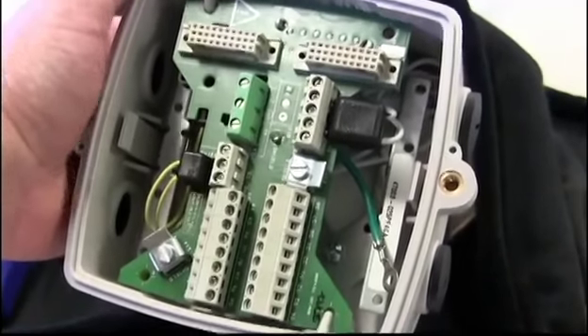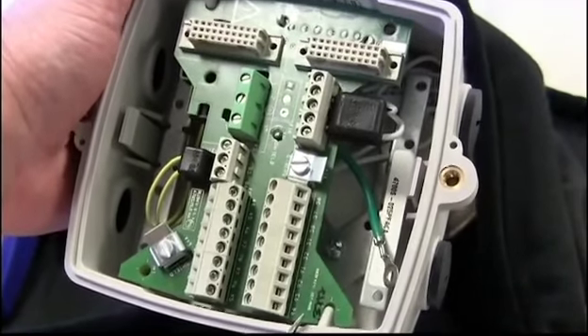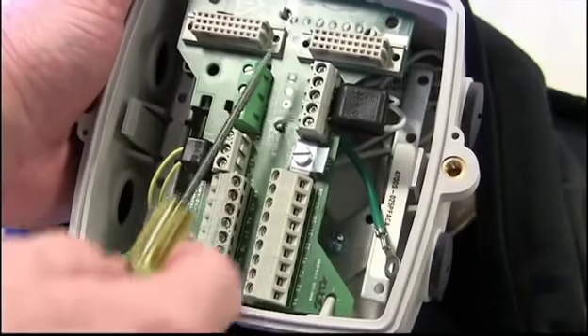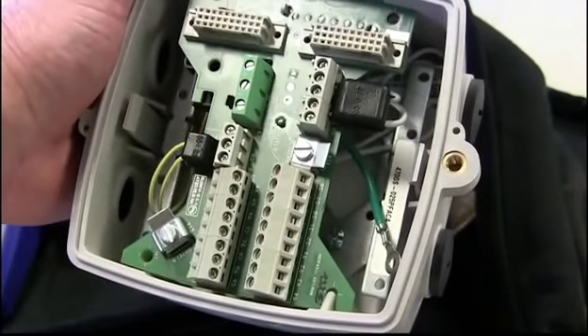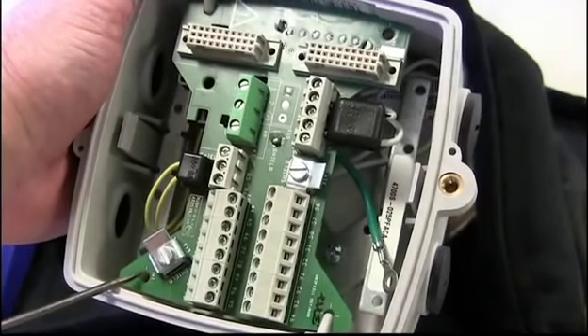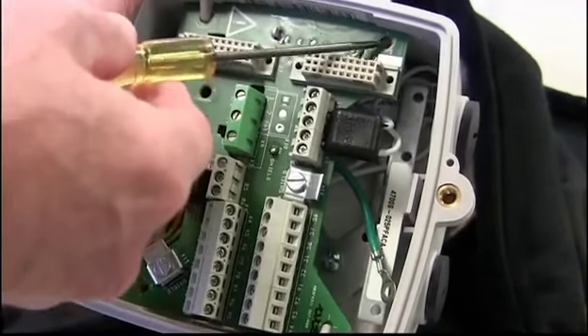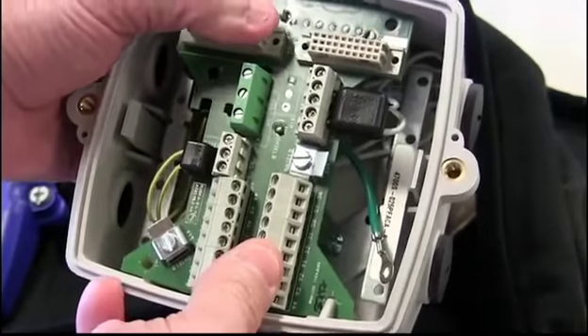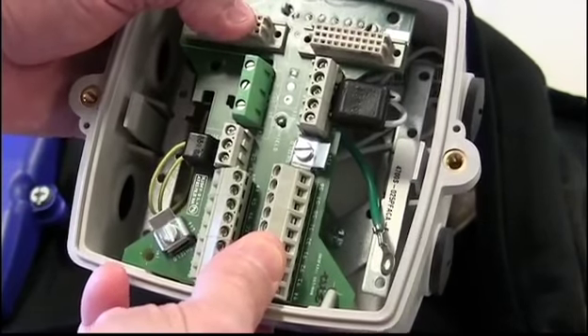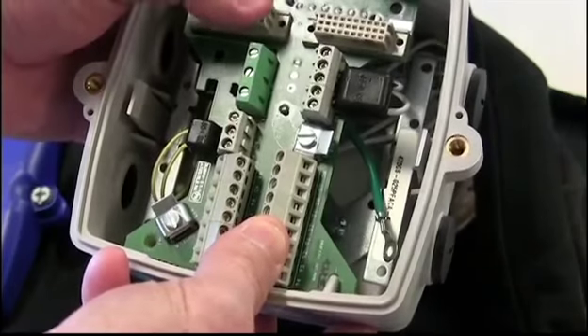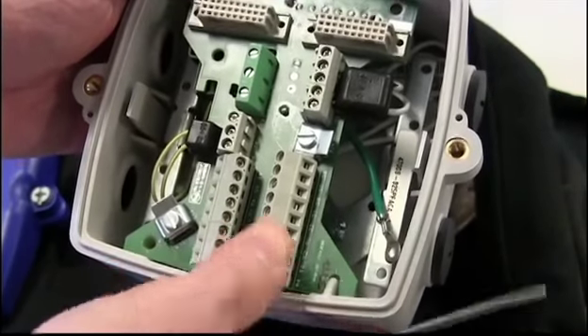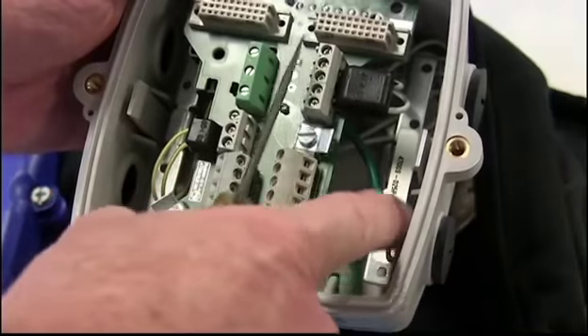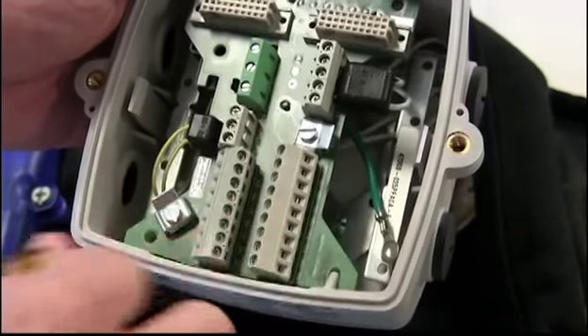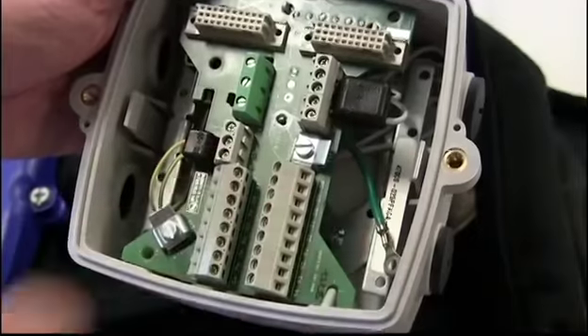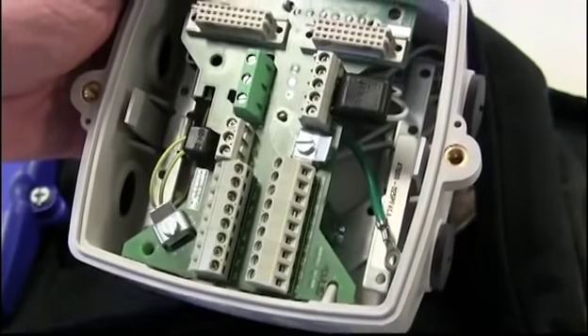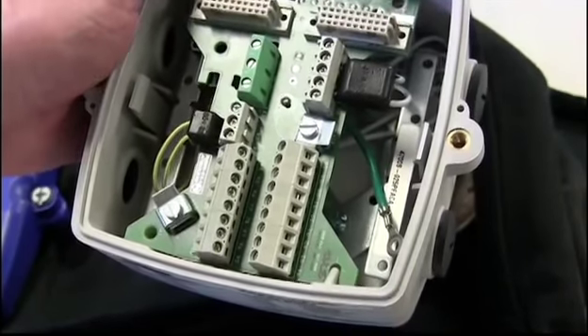Now that the connector board has been placed in the housing of the flow tube, seated correctly on top of the sensor prom, now's the time to secure the board with 2 screws, one here and one there. So this secures the connector board down in the housing so it doesn't move. And at the same time there is a shield ground that needs to be tied into the mounting plate in the flow tube. So when we come back, we will place the transmitter on top of this assembly.